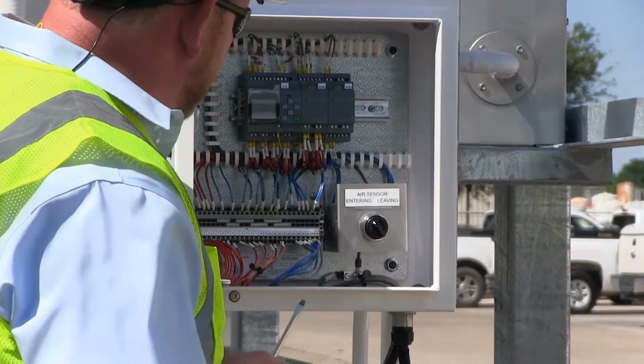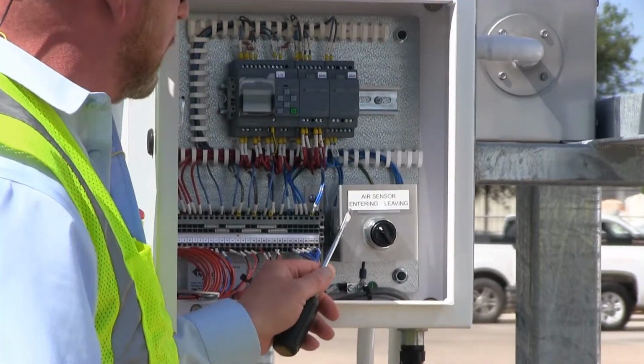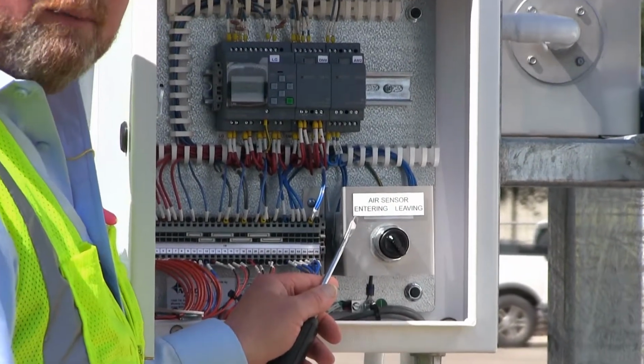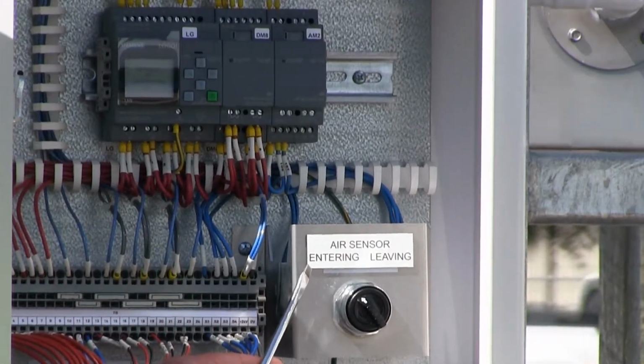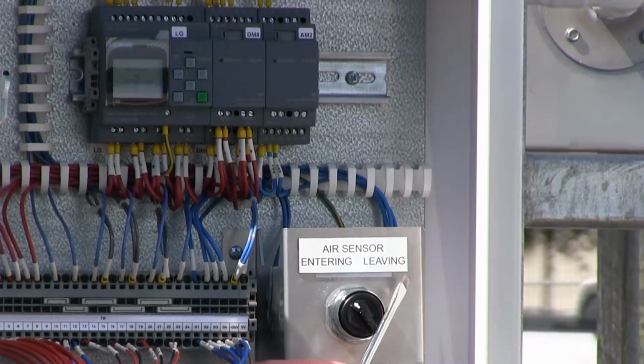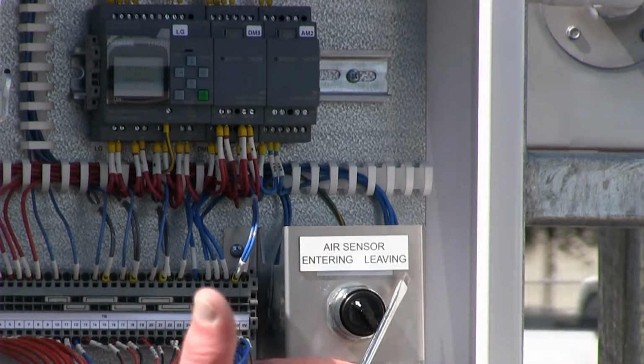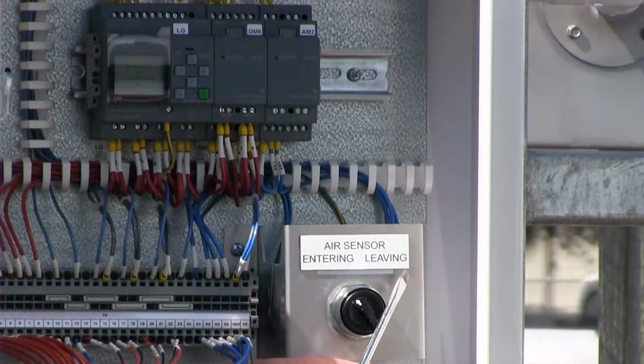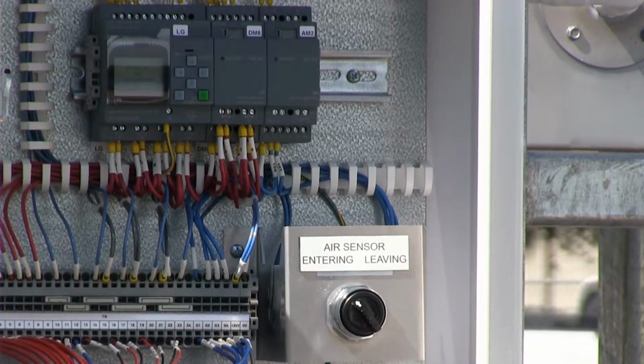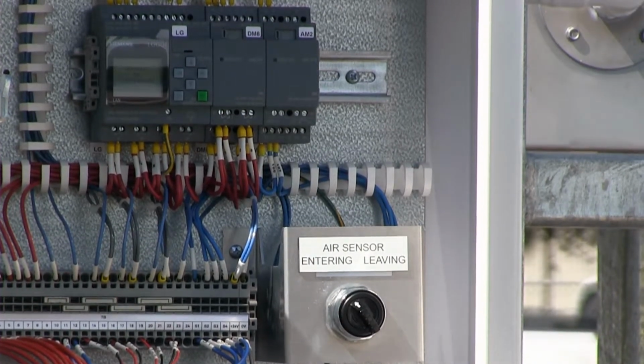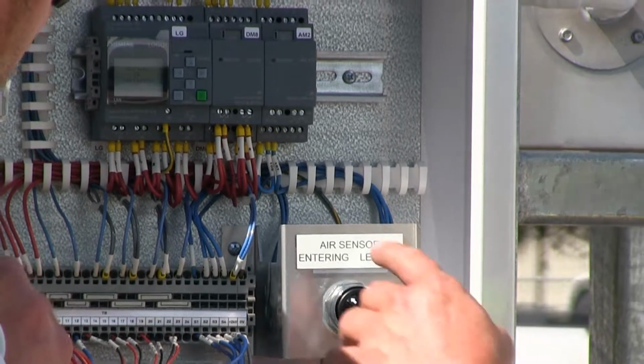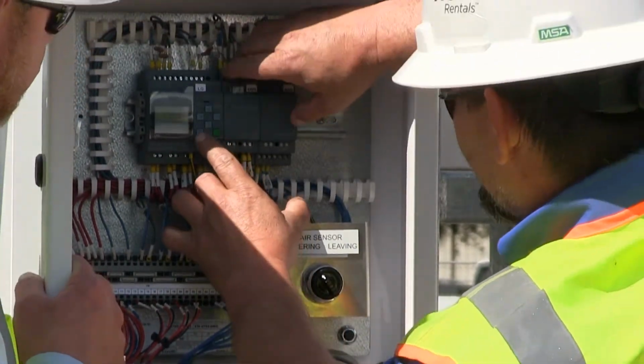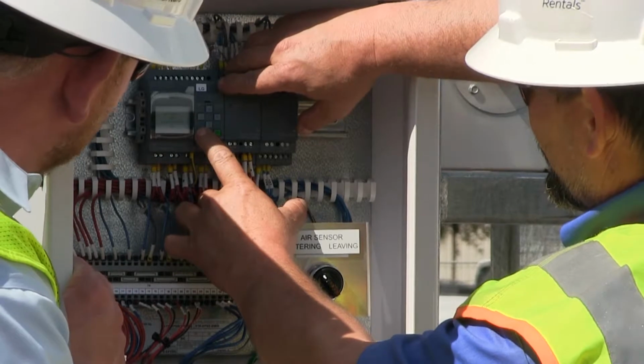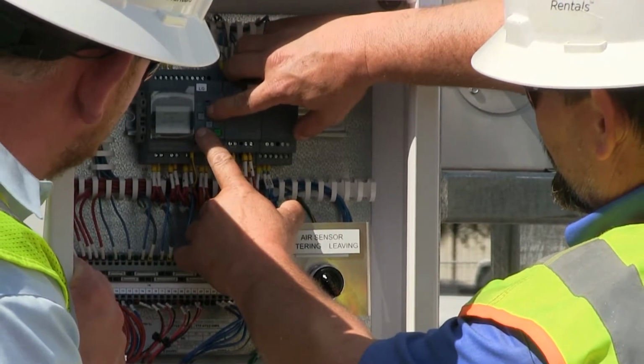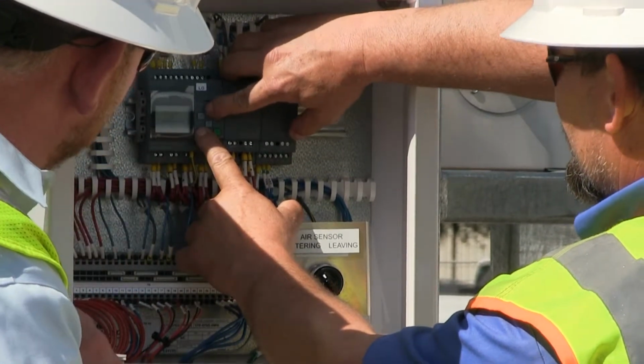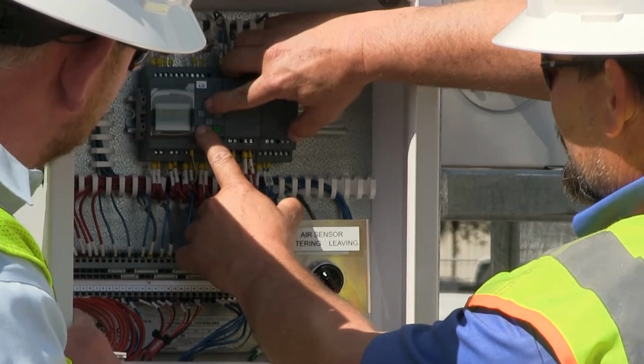At this point, we have a decision to make whether we're going to control the unit through entering air, which is coming into the machine, which is pretty standard, or we can control it to outlet temperature, meaning set it at 75 degrees on the inlet, 55 on the outlet or leaving air temperature. We're going to go over the settings of the thermostat, and that's done by holding down the escape button. You'll notice that the temperature set point right now is at 50 degrees. And you can raise the temperature up to 52, 53, instead of 50.